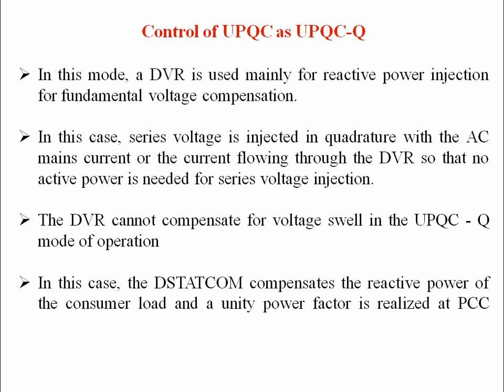Now, control of UPQC as UPQC-Q. In this mode, a DVR is used mainly for reactive power injection for fundamental voltage compensation. So this DVR — the Dynamic Voltage Restorer — is used for reactive power injection. In this UPQC-Q mode, the DVR is used for fundamental voltage compensation. The series voltage is injected in quadrature with the AC mains current, which we have already discussed when studying the UPQC-Q configuration.